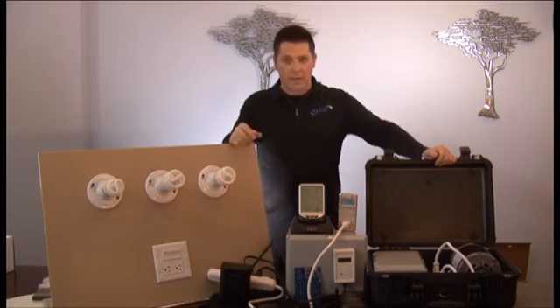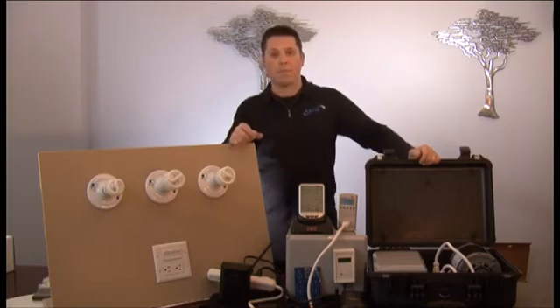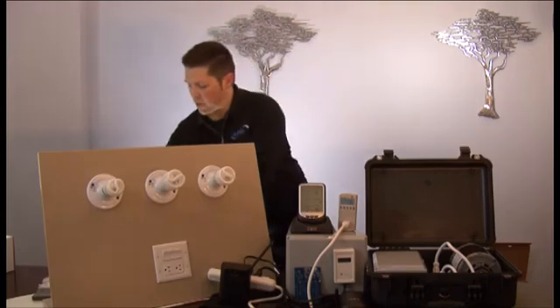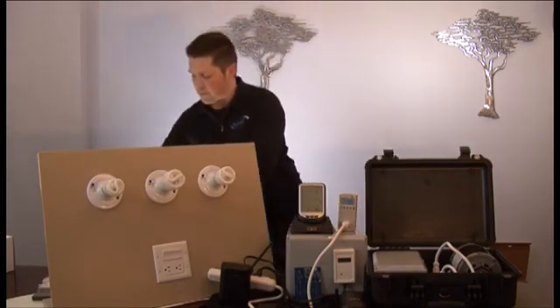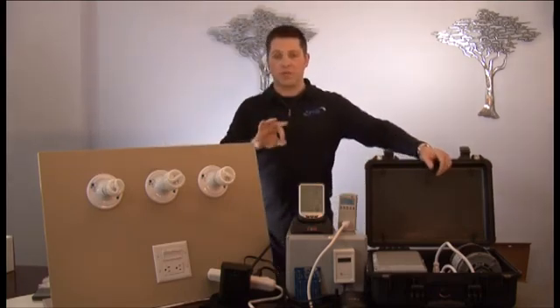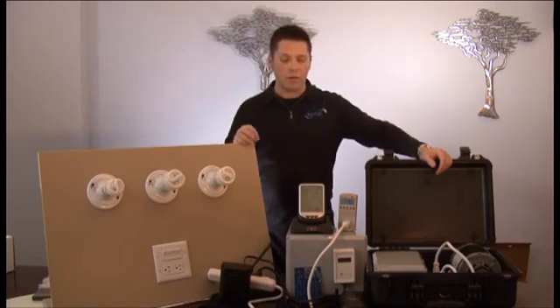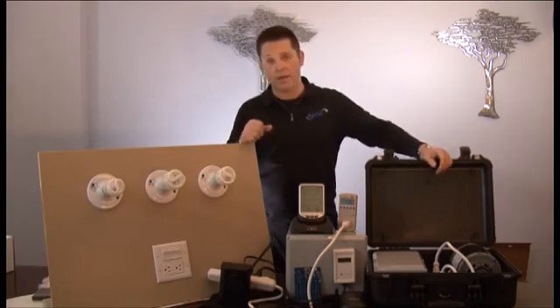It used to be that the neutral pathway had a very light load. When I was talking about storage of electricity and cleaning the power earlier, we were talking about the fact that your electrical system has 3 pathways, A to B, A to neutral, and B to neutral. Well, that A to neutral and B to neutral is different now than it's ever been in American history. Why? Because of switching power supplies.